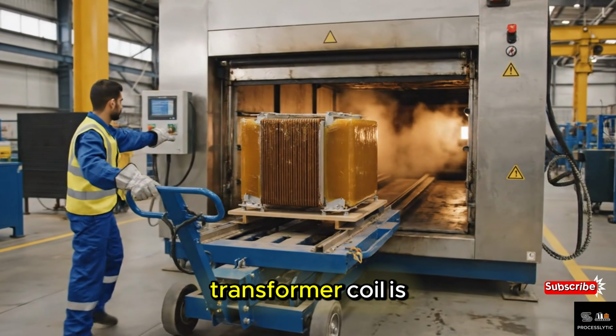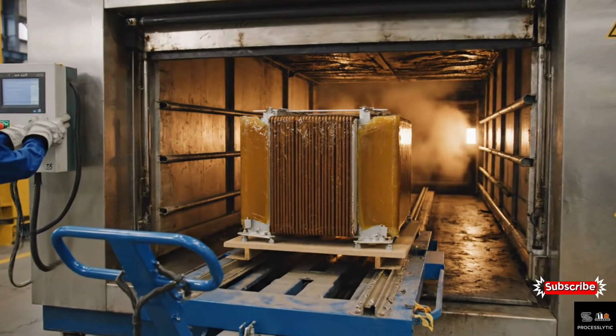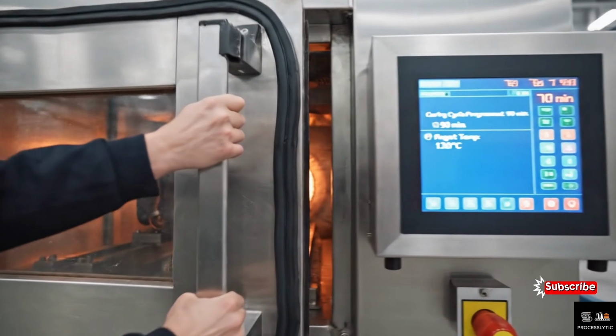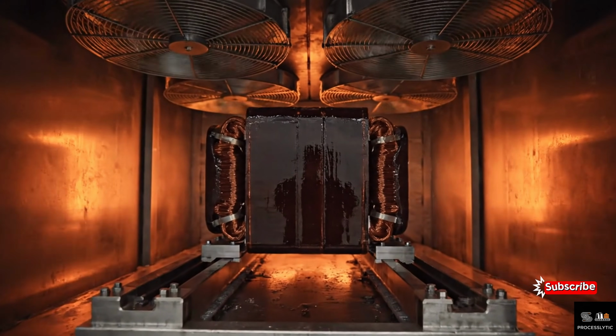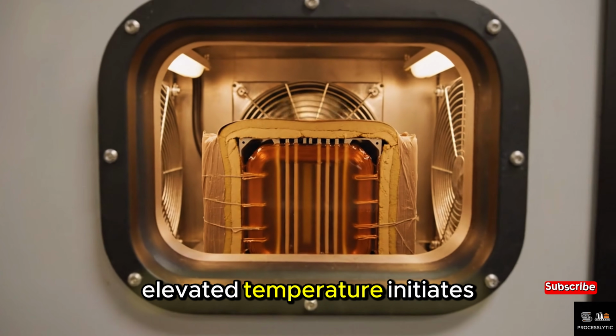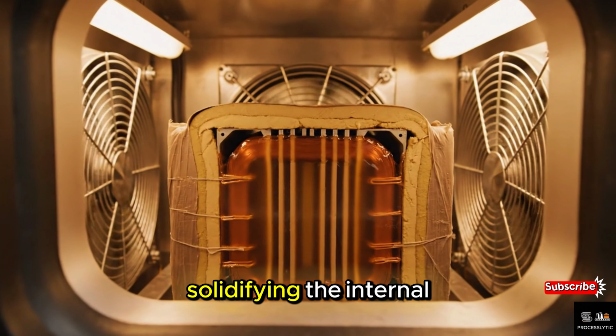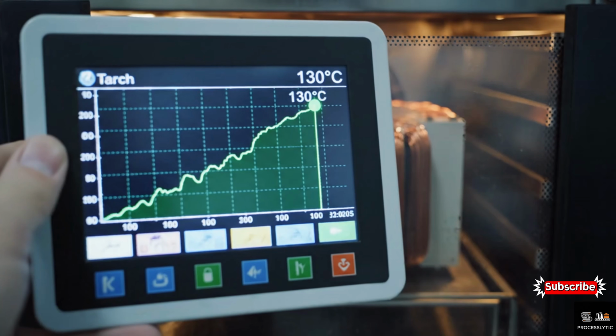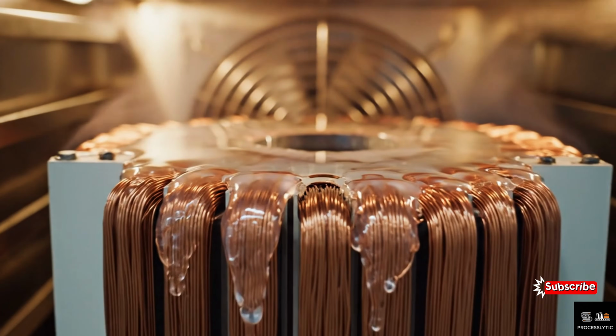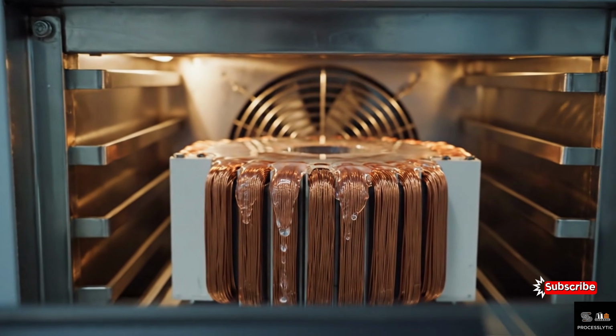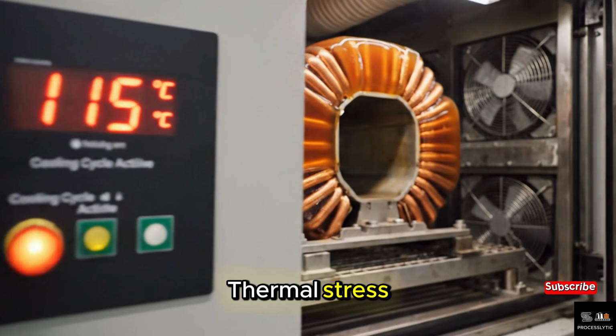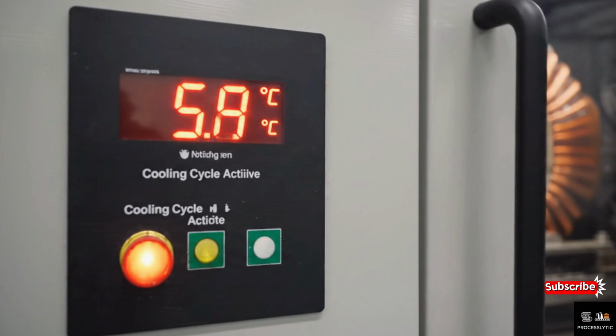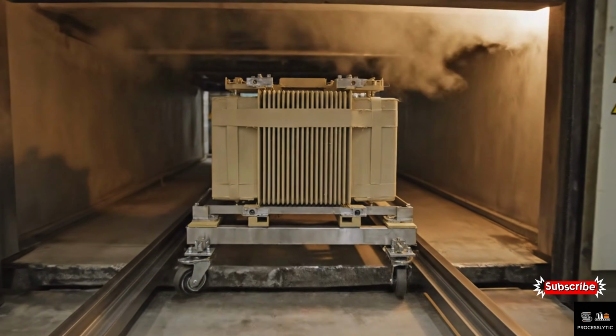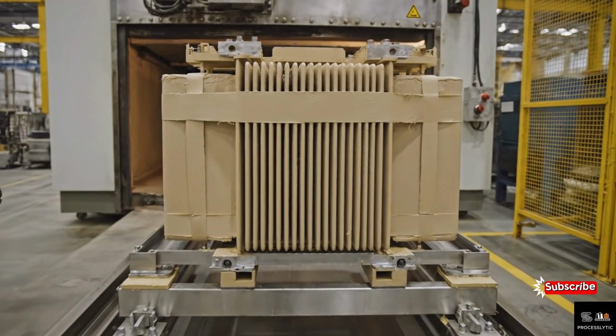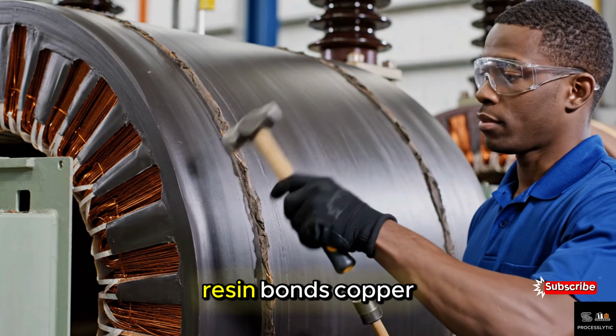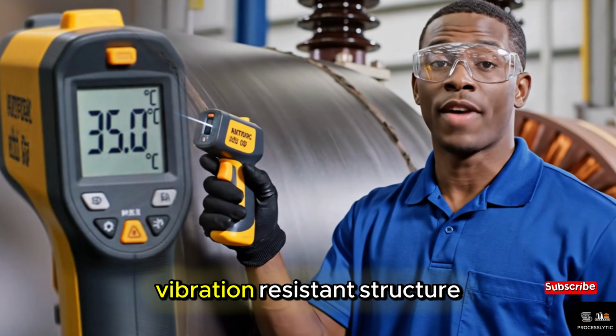The resin-saturated transformer coil is transferred into a controlled thermal curing oven. Elevated temperature initiates epoxy resin polymerization, solidifying the internal winding structure. Controlled cooling prevents thermal stress and preserves winding alignment. The cured epoxy resin bonds copper windings and insulation into a rigid, vibration-resistant structure.